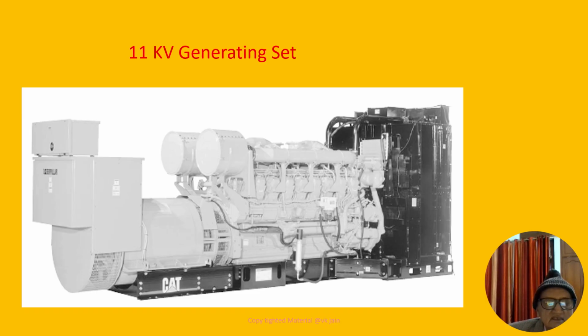If the campus is very large and buildings are quite apart, it is not possible to work with a 430 volts or 415 standard voltage generating set and take hundreds of cables in the campus to feed electrical load in various buildings in the campus.